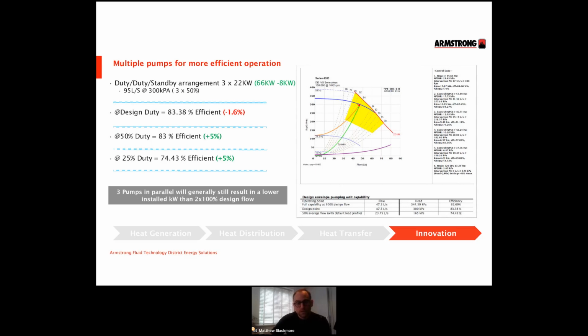Now, somebody alluded to earlier, we oversize equipment terribly. We very, very rarely operate at design duty. Most of our time is spent at part load. We accept that we live in a part load environment, a part load world, but we still select plant and size plant based on the worst case scenario. So if you know this is a fixed network load, in this instance it is, we can make genuine savings for existing networks just by employing a slightly different approach that's supported by CP1.